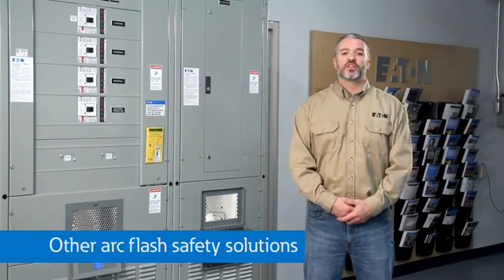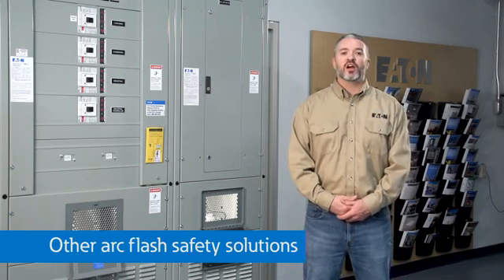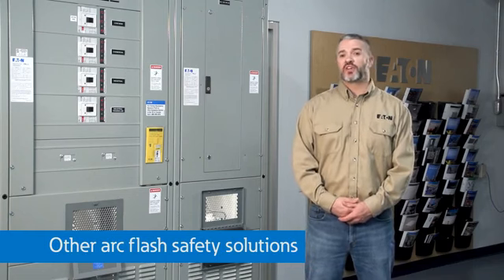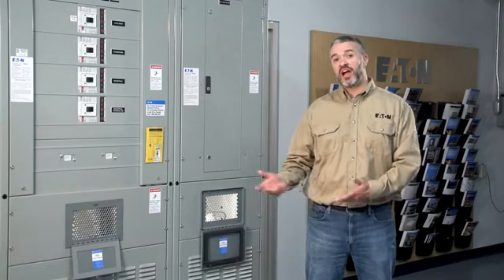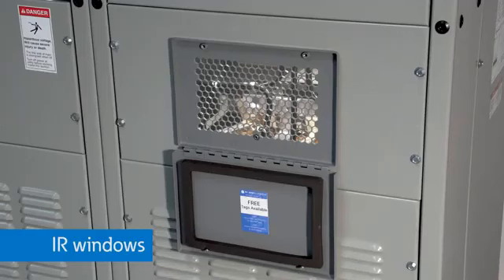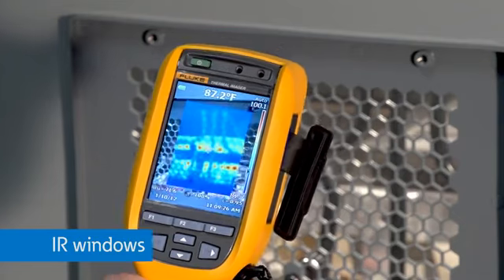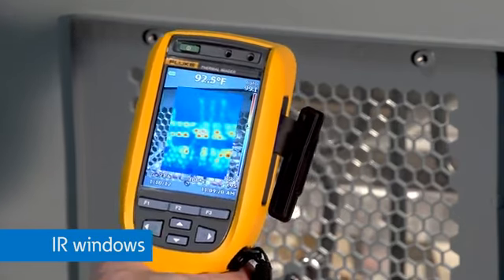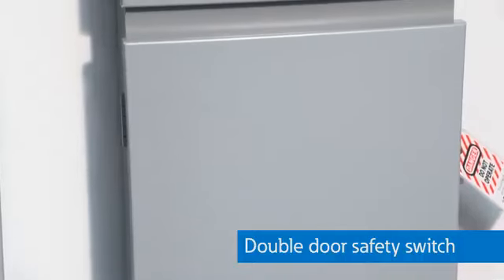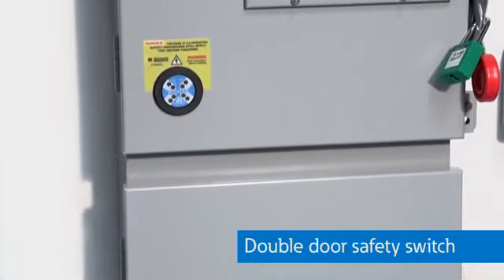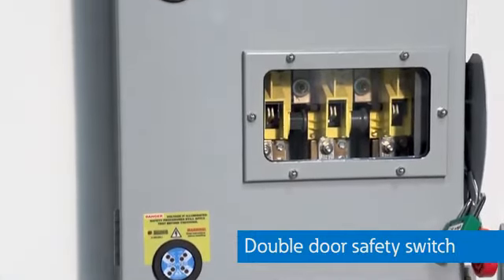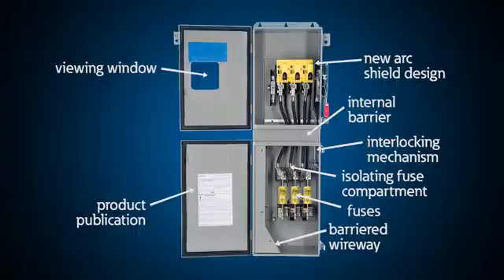Although there are many other solutions for arc flash safety, here are a few more that we typically highlight for our visitors here at the PSEC, like these IR windows that allow you to look for potential issues inside your switchgear, switchboards, or other equipment like busway. This double door safety switch allows you to install fuses and make connections on the load side of this switch without being exposed to the line side or energized connections.